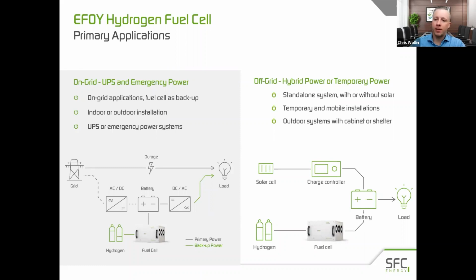And then if we're looking at a hybrid primary power scenario, this is where the EFOY hydrogen fuel cell would be paired together with solar and or wind to charge a larger common battery bank, which would provide power to all of the site loads. The solar and wind would be sized to carry the loads and maintain the battery bank during the parts of the year when enough production capacity is available. And the fuel cell would turn itself on and off as required to provide supplementary power to cover any production shortfalls during the fall and winter months or during periods of bad weather, ensuring that the battery is maintained and the site loads are never short of power.